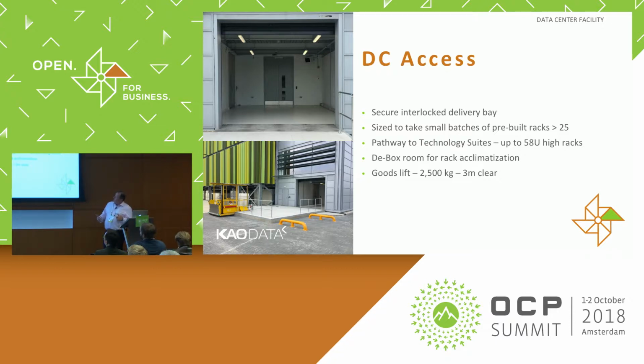One thing we've focused on is making sure we can cope with up to 58U cabinets, really giving people the ability to use the power in the footprints within the data hall. Sometimes with smaller cabinets people run out of cabinet footprint before they run out of power. So giving them the ability to use 58U cabinets, which can be rolled in straight onto a loading dock via tail lift or a curtain-sided lorry using a scissor lift, means you can wheel them all the way through goods lifts up onto the 2 floors above ground where the data centres are.